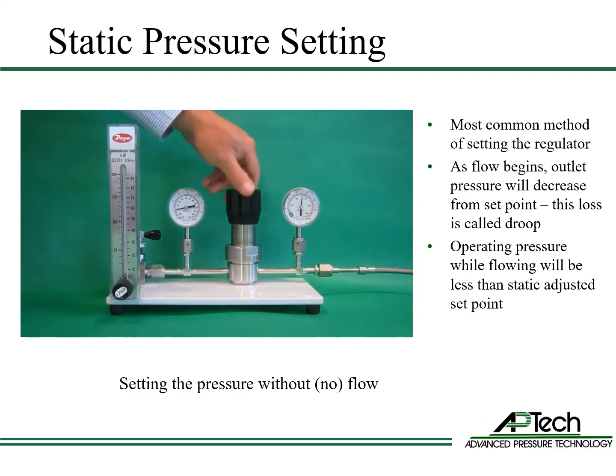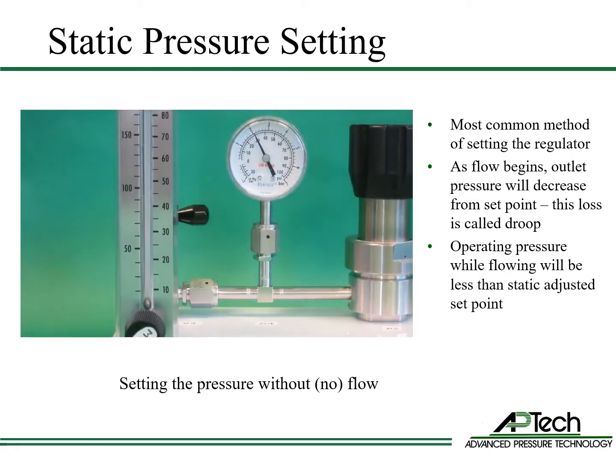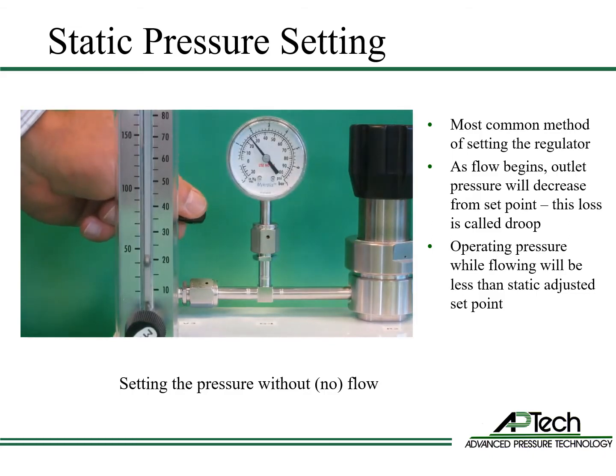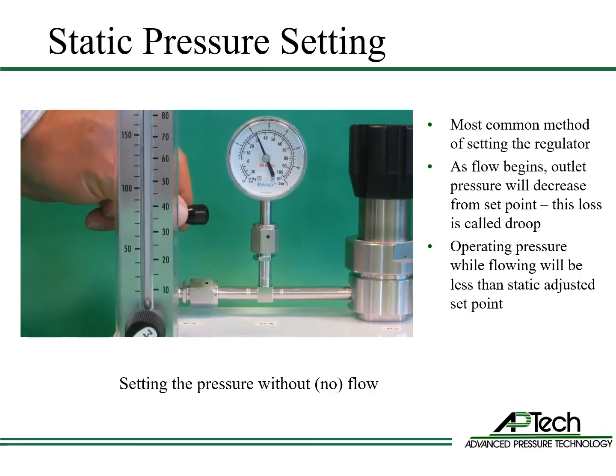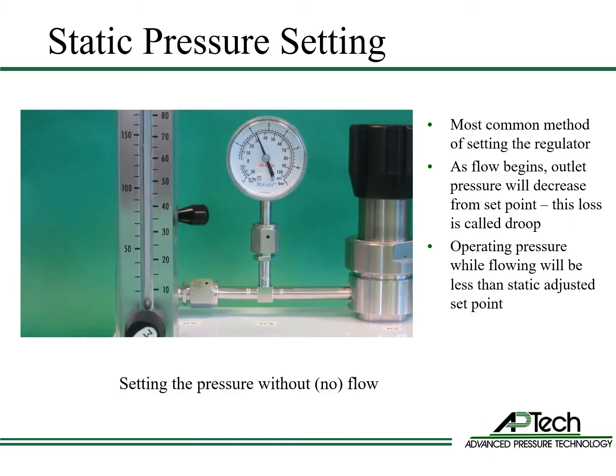Now we'll demonstrate two methods to set the outlet pressure. The most common method is static pressure setting, which means setting the pressure regulator with no flow. As flow begins, outlet pressure drops compared to the set point due to droop. When flow stops, the outlet pressure will rise slightly above set point due to creep or lockup. This is normal and will be explained in detail in later training.